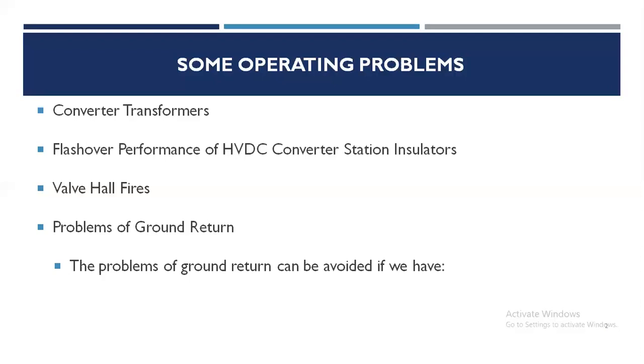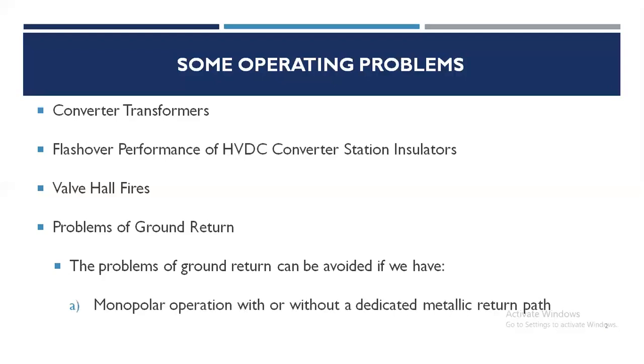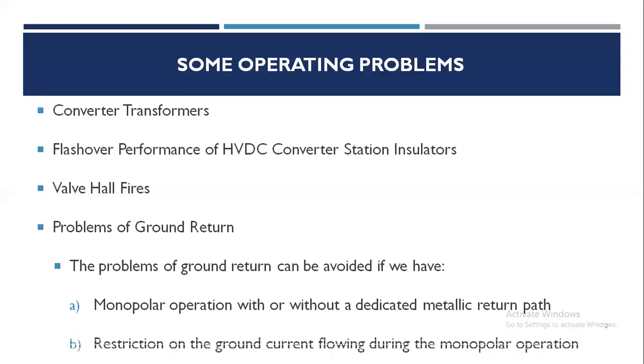The problems of ground return can be avoided if we have monopolar operation with or without dedicated metallic return path. The scheme without a dedicated metallic return path is grounded only at one of the terminals and results in lowest cost. In this case, monopolar operation is feasible during the converter pole outage but not during the HVDC line conductor outage. And the second one, restriction on the ground current flowing during the monopolar operation.